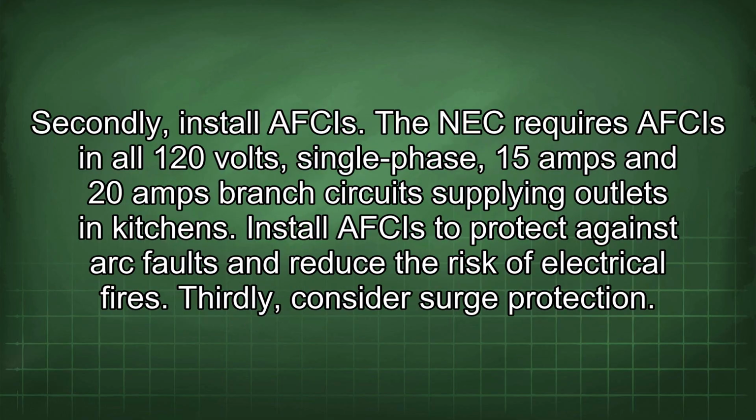Secondly, install AFCIs. The NEC requires AFCIs in all 120 volts, single phase, 15 amps and 20 amps branch circuits supplying outlets in kitchens. Install AFCIs to protect against arc faults and reduce the risk of electrical fires.